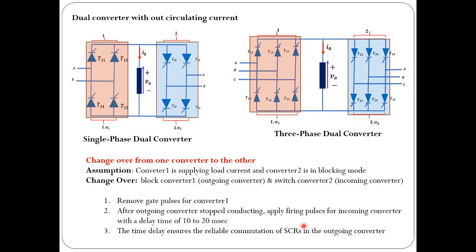Of course, the procedure is the same for a 3-phase dual converter also. If you want to change over from one converter to the other in 3-phase dual converter operation without circulating current, you should follow the same steps. You should be very, very careful. There should be a time delay.